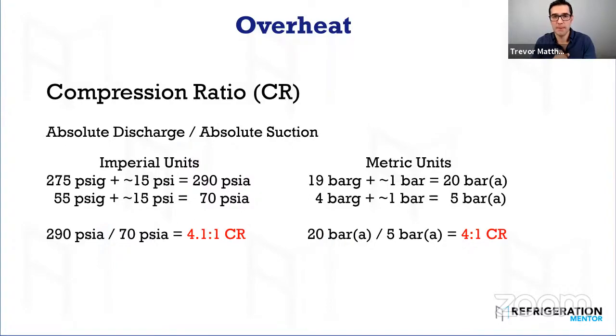That's using psi. But if you take that same 25 for these examples and drop it on the suction, you're at 10, 12, a 12-to-1 compression ratio. So suction pressure drop is real bad. And if you have a high pressure drop in your suction line, either there's a design issue, because you shouldn't have more than 2 psi, and even that's kind of high, or you've got a plugged filter dryer or something plugged inside that suction line. You need to fix that.